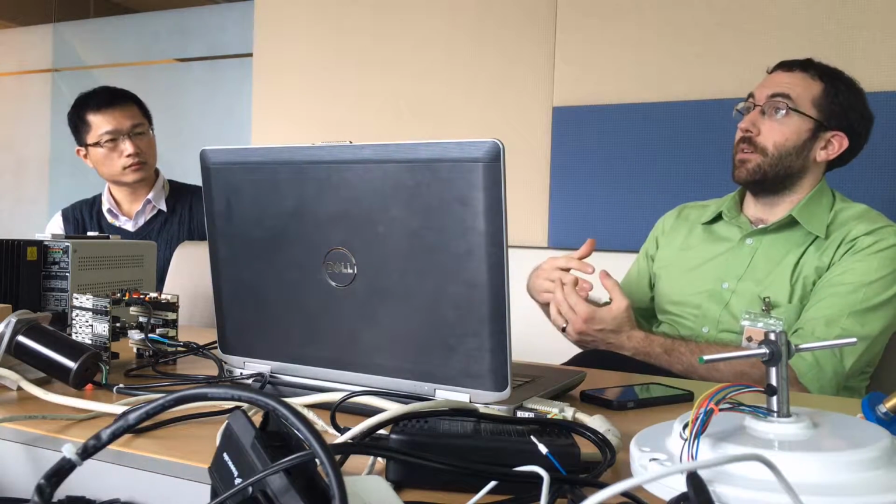It's designed to be iterative. So if you click the button and it fails, it'll prompt you and say it failed, but it's updated the configuration values, please try again. So that's the thing to watch for when you're doing the inertia identification, is that it'll tell you if it was able to adapt or if it wasn't able to adapt. And so it might take multiple tries to get it to actually complete.